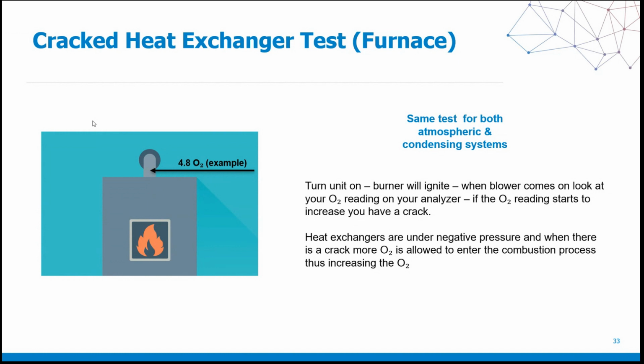So depending on if your carbon monoxide levels are high or not, the oxygen percentage, but also the remaining CO and CO2 numbers, are going to set you on a direct path as far as what your recommendations are. Do you have a crack in the heat exchanger? Is it an issue with the rings on the heat exchanger? Whatever it is, as it relates to the heat exchanger, you can now develop a plan of action, and you can also fully ascertain how safe the conditions are for people to actually be there. But again, remember, the crack's not going to get smaller, it's only going to get bigger.